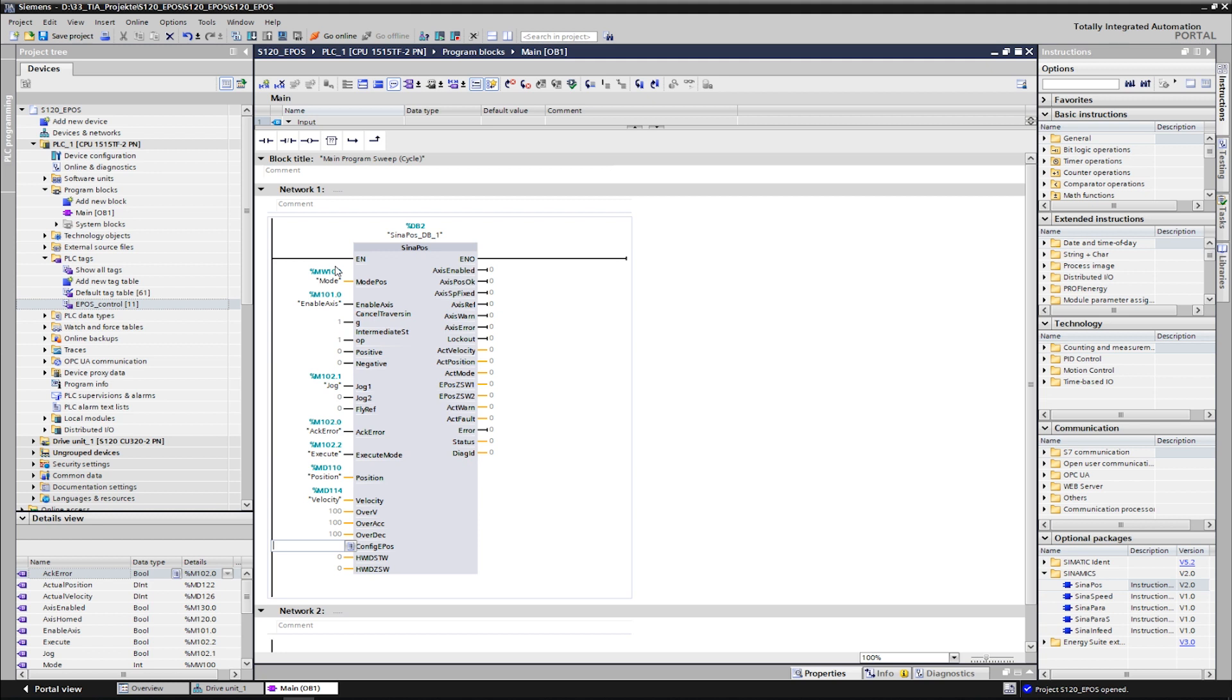In the ConfigEPOS input, further functions of the axis are broken down in binary form. For example, bit 0 and 1 stand for the shutdown functions OFF2 and OFF3 and are therefore set to 1 by default. Bit 2 activates the software limit switches. Since we want to use these, we additionally set bit 2 by specifying the converted decimal value 7. The value 7 results when the first 3 bits of the control word are set. The list of all control bits can be found in the manual.